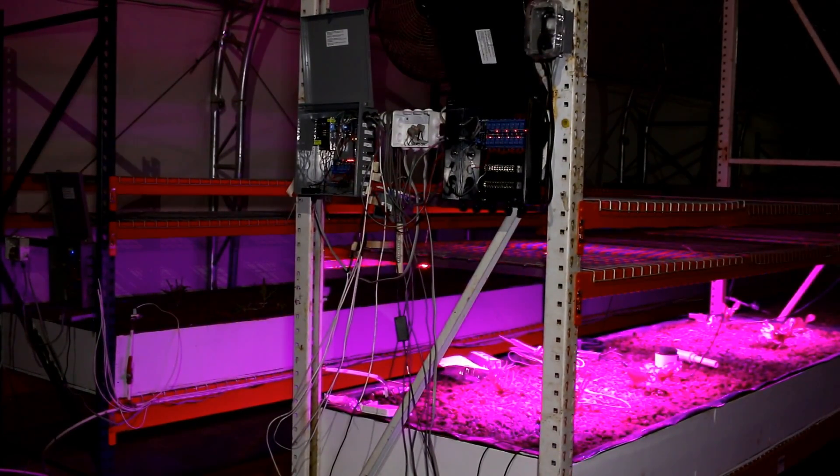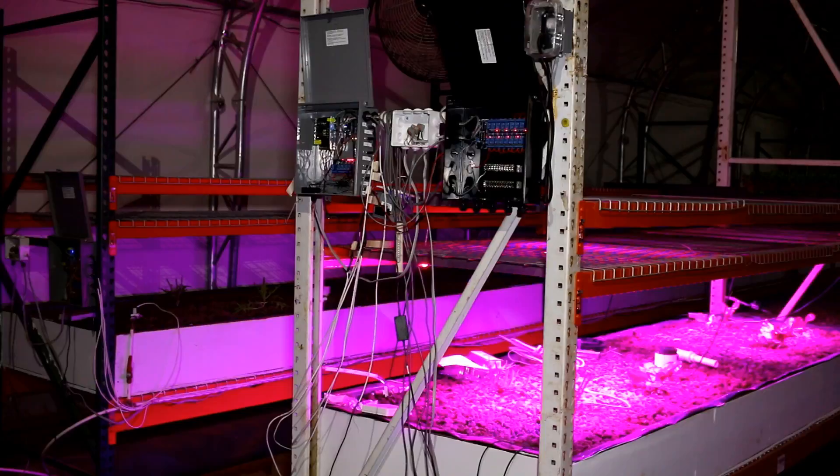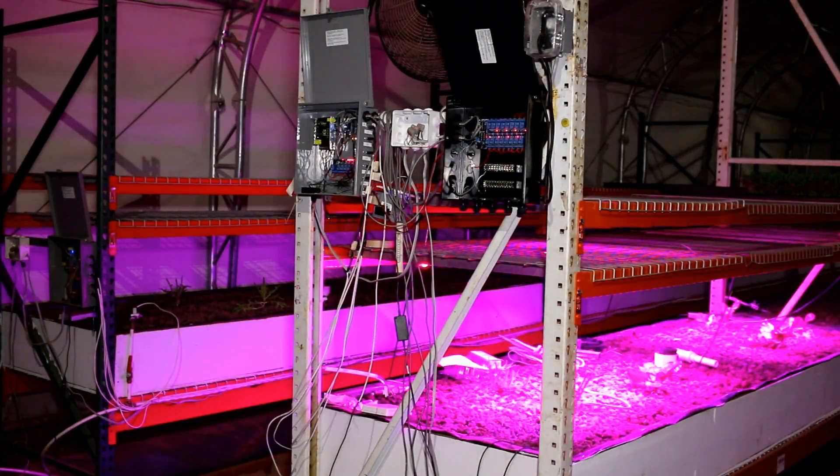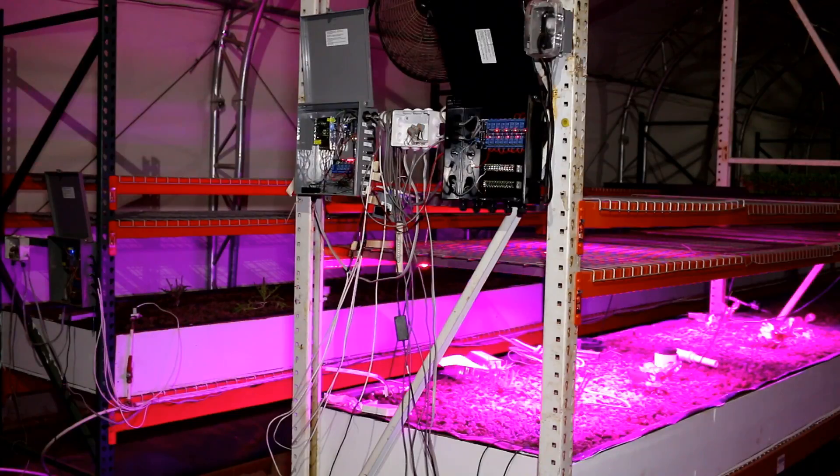So I'm walking over to the generator switch here now, and I am flipping over lights, the fridge, oh those are backwards. Oh, that turned on, oh that's good. Goes lane 1, lane 2, lane 2 is now on generator power. Lane 3 is now on generator power. Lane 4 is now on generator power. Now I'm going to kill main power to the building. And there we go.